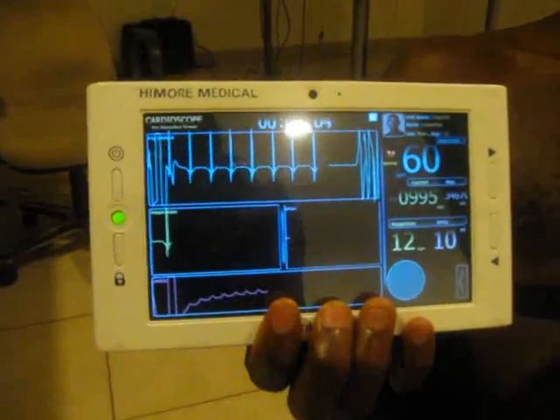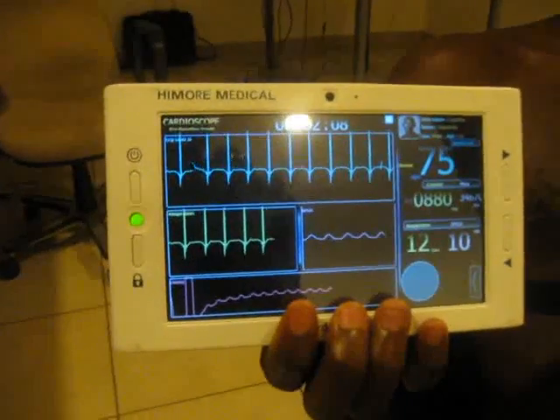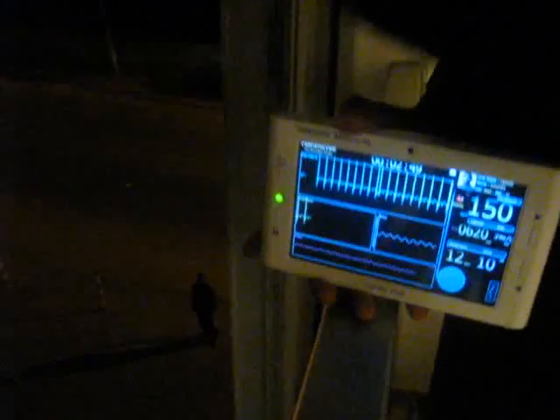A key advantage of this health monitor is that the patient can move — the patient can move in the room, go out of the room, and even go out of the building. As you can see here, we still receive the cardiac signal of the patient and process it in real time, even when we are on the third floor and the patient is on the ground.